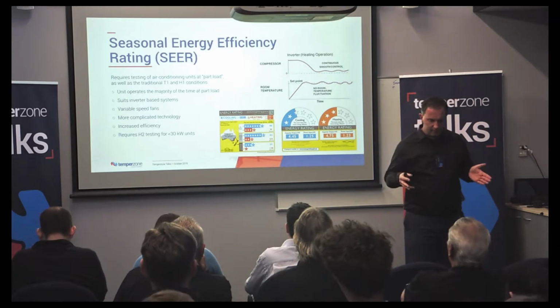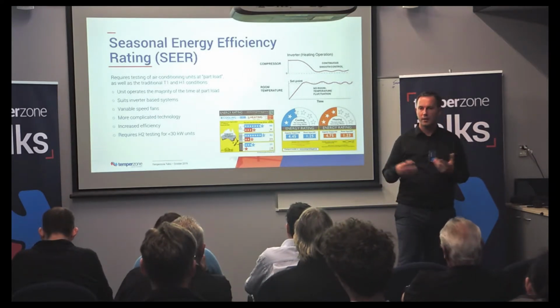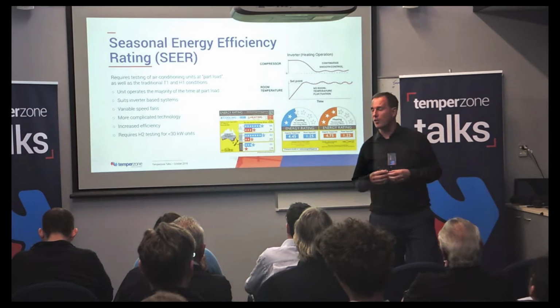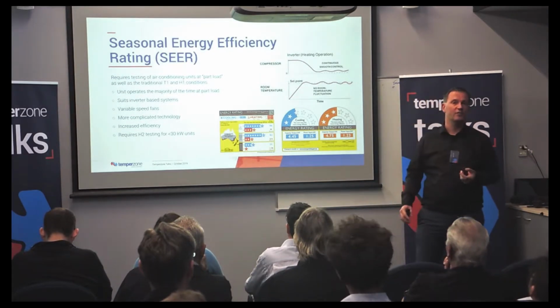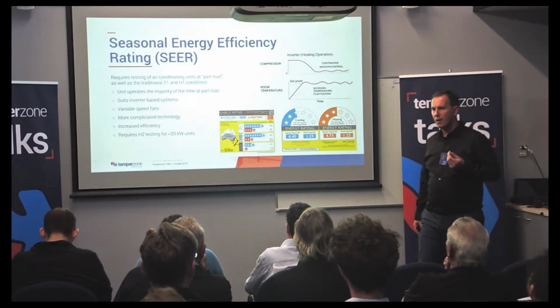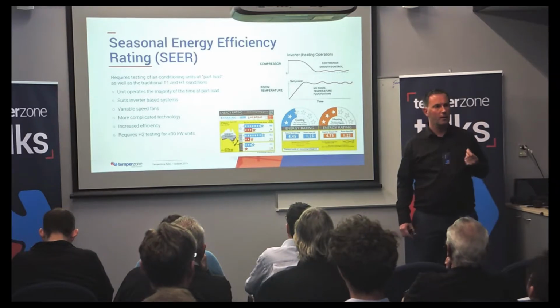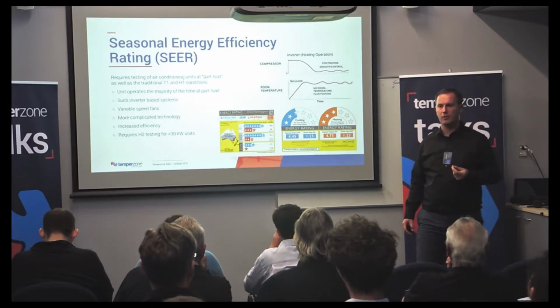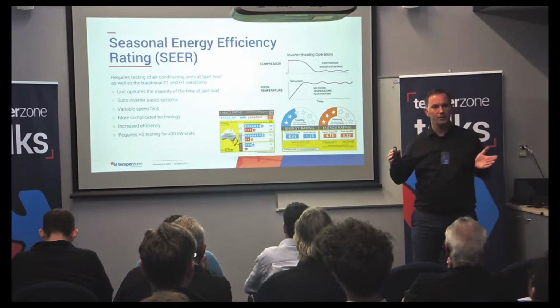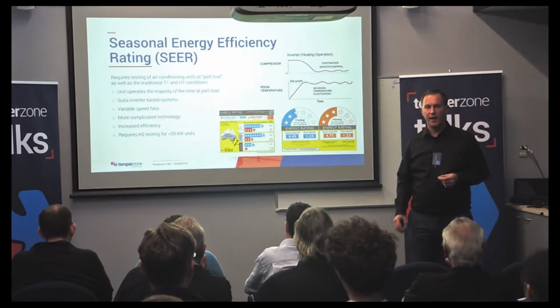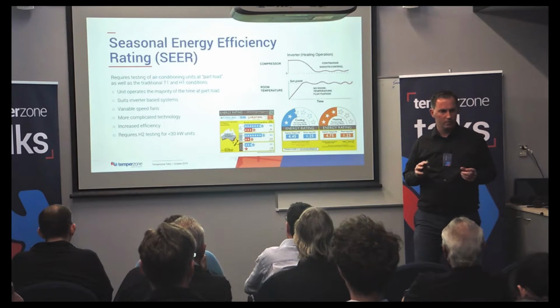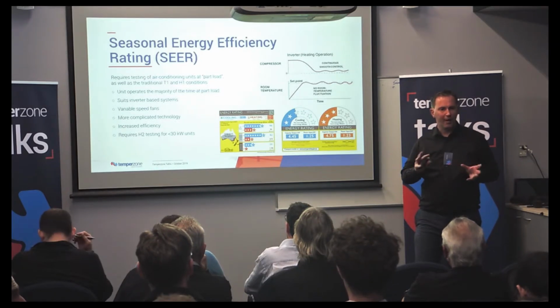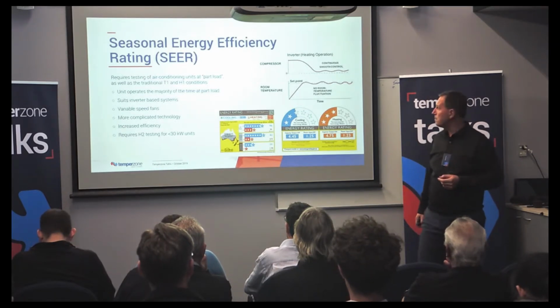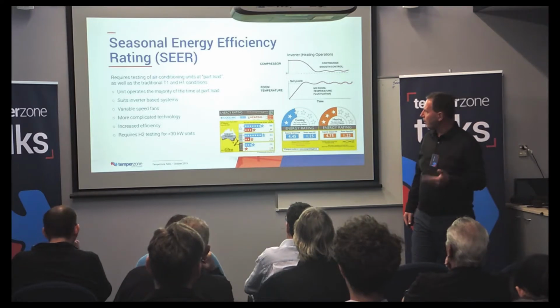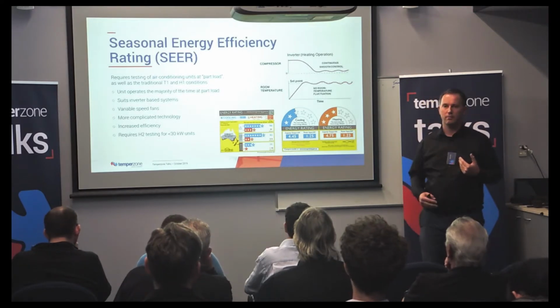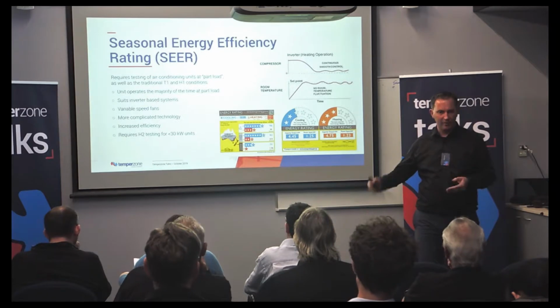Looking at the key trends driving the industry, the first is the move from a fixed rating point for air conditioning products to a seasonal energy efficiency rating. This test method requires us to test our units at a number of different test conditions under different loads, which is where we get the part load efficiency from.